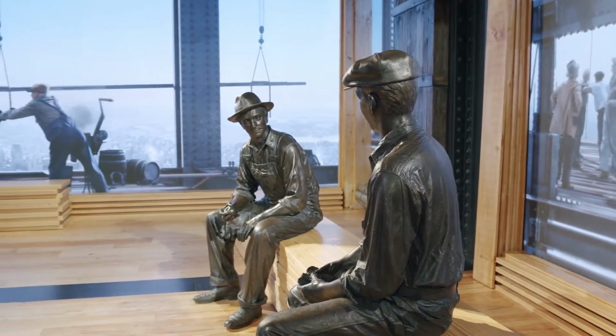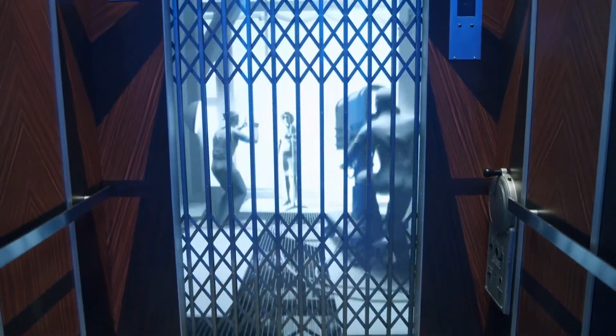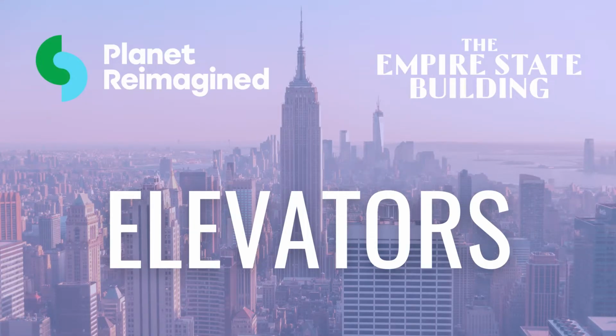One of the first changes was the elevators. Regenerative brakes preserve energy that would have been lost to friction, and a dispatch system ensures that riders are grouped together depending on their destination. What does it mean to retrofit an elevator specifically? Instead of using brakes, which generate heat through friction and nothing else, you control the downward speed with regeneration, the exact same concept as what you use in a Tesla or in any other car that uses regenerative braking.